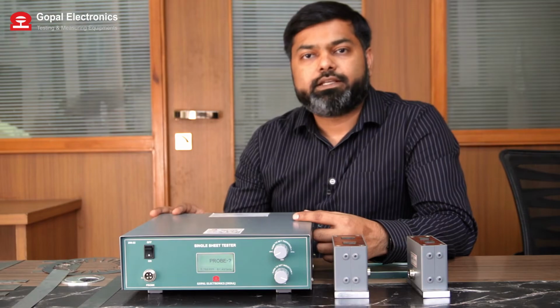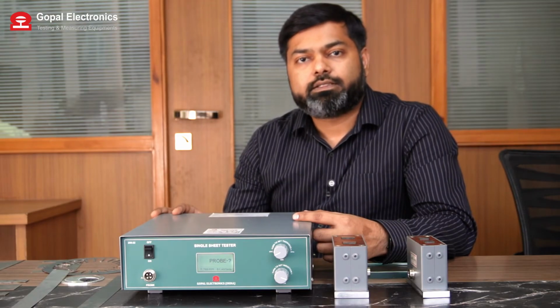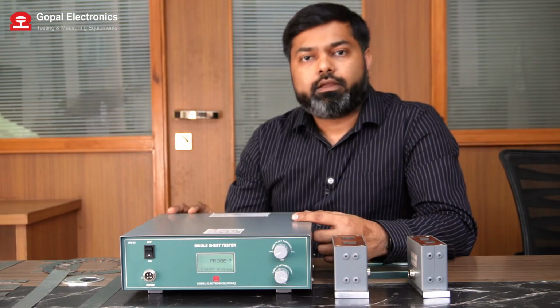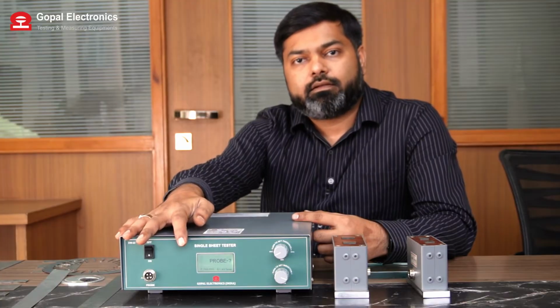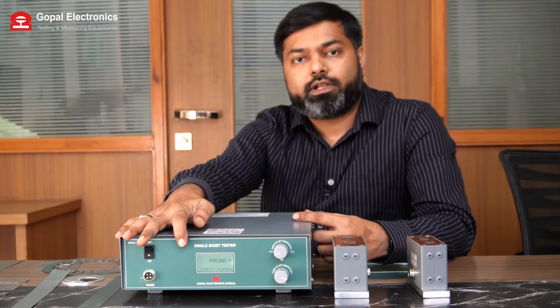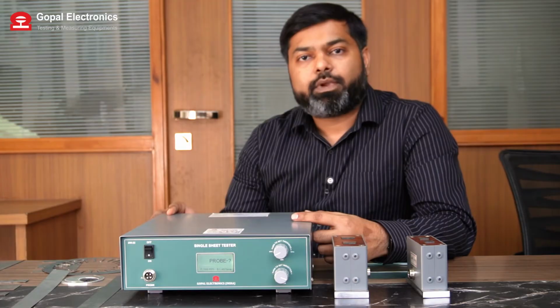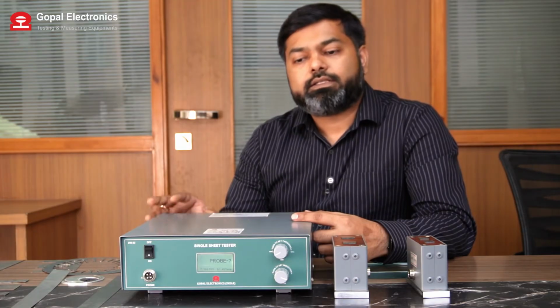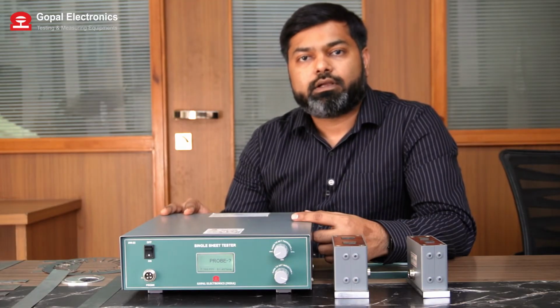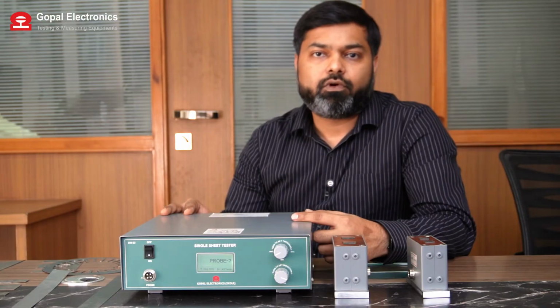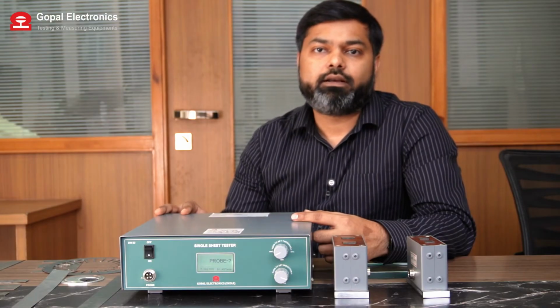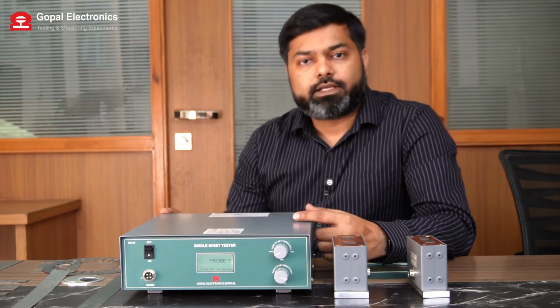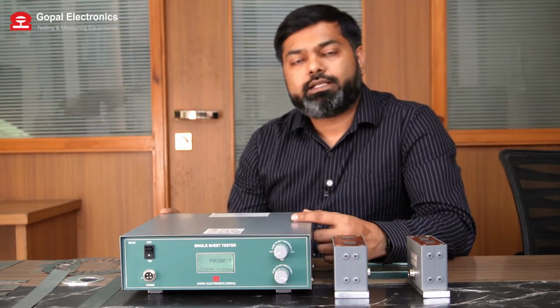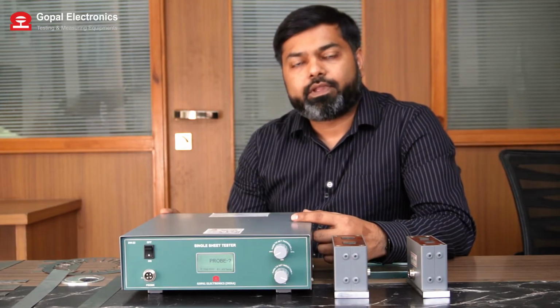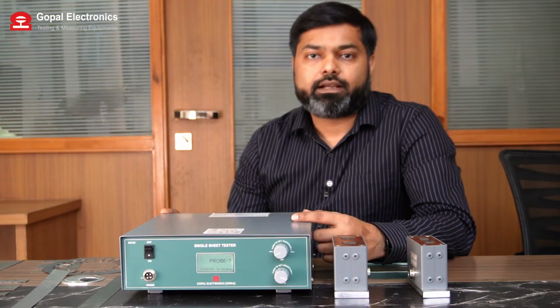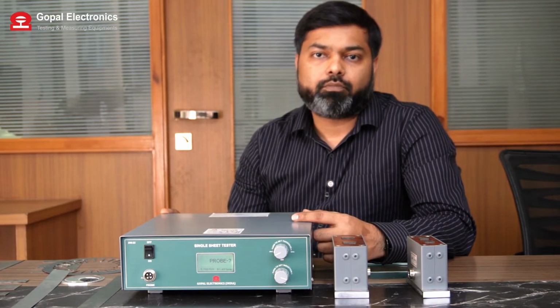First of all, this machine is capable to test at both 50 Hz and 60 Hz frequency. 8000 pixels graphic display is provided for easy visualization. Universal power supply provided. The same machine you can use at 110 volt auxiliary supply and 230 volt auxiliary supply. Flux density you can set from 1 Tesla to 1.8 Tesla. Thickness of the sample you can set from 0.1 mm to 0.7 mm.